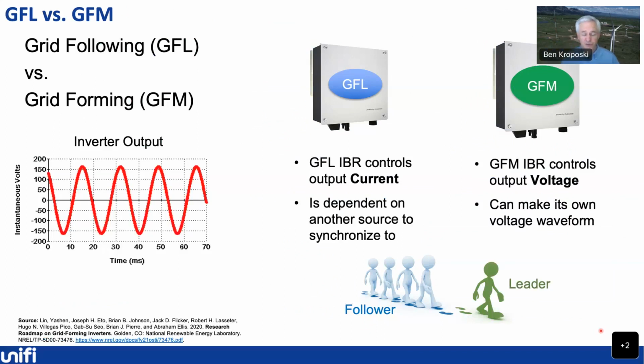Now, historically, everything that we've been building with large-scale bulk power integrated inverter-based resources has been using a grid following capability that basically is controlling the output current, and it's completely dependent on another device like a synchronous generator to develop that voltage waveform in order to synchronize to. And we would think of these as followers in the system. And then what we've been working on is these grid forming controls, which are actually controlling the voltage waveform.